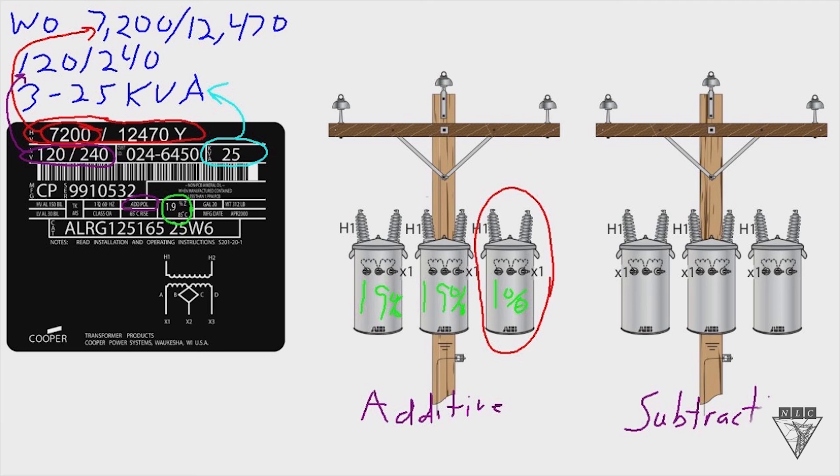And this can be a hazard, especially in the middle of the night. If you come up on a connection, you're like, what is this? I've never seen this before. It could actually be a safety concern. So although electrically it will work, you want to try and find three transformers that have the same polarity, just to make it so the connections are traditional and look the same.